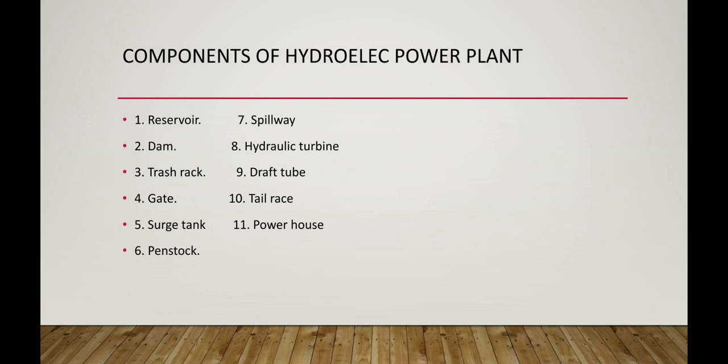Then the next one is a penstock. The penstock is used to carry the water from dam to the powerhouse. It is generally a closed pipe. Penstock is a circular pipe having very long length, laid down from the dam up to the turbine room. Penstock carries the water under pressure from water stored in a dam or reservoir. It is generally made up of steel with reinforced concrete.